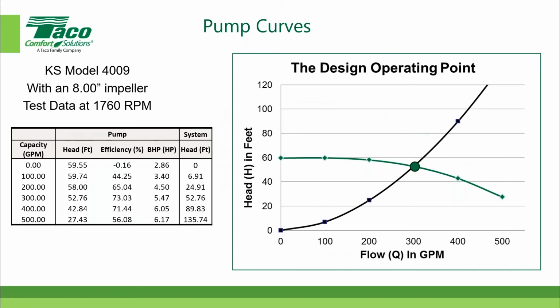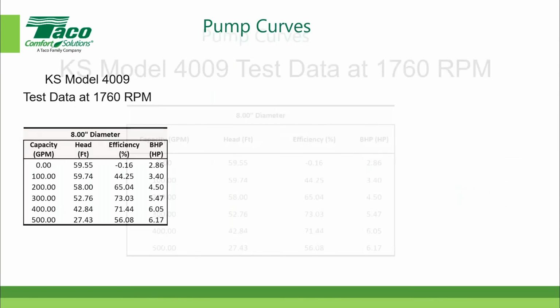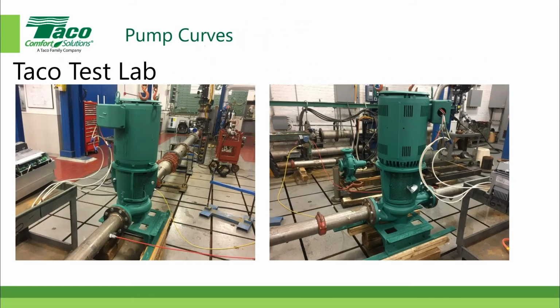That's a great question. So when it comes to laboratory data, let me go back to the photograph here, make it a little easier. If you'll notice on the suction side of the pump, let me kind of point things out here. On the suction side of the pump, we have a minimum of 15 pipe diameters, and you can barely see this yellow tubing connected for the suction pressure reading. You can see it a little bit easier here on the discharge where this red tubing is connected. And the pressure drop between the flange connection and the straight run of pipe, remember this is the same as the diameter of the outlet, it's negligible.